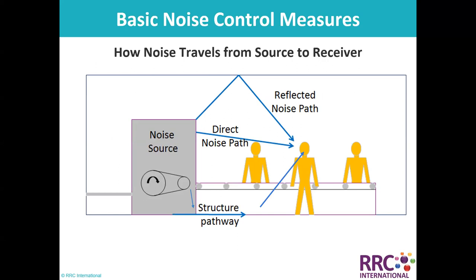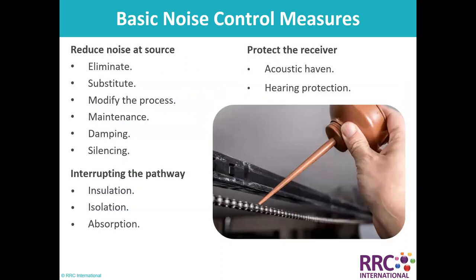Basic noise control measures follow the hierarchy of how noise travels from source to receiver. Reduce noise at source by eliminating, substituting, modifying the process, maintenance, damping, or silencing. Interrupt the pathway through insulation, isolation, or absorption. Protect the receiver through acoustic enclosures or hearing protection.